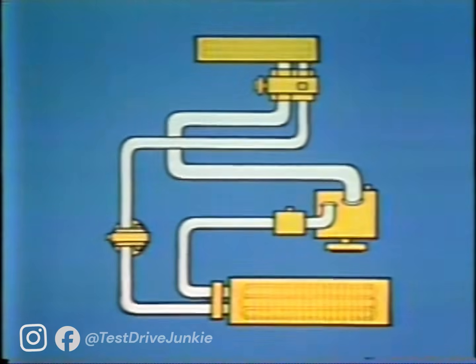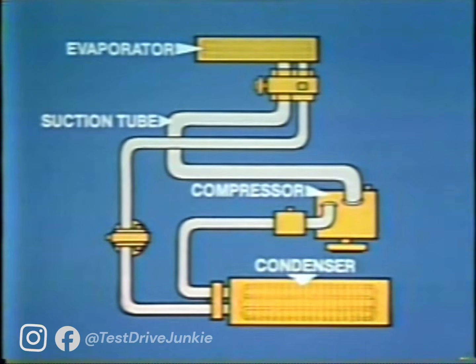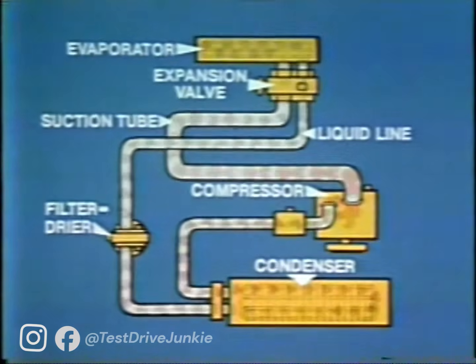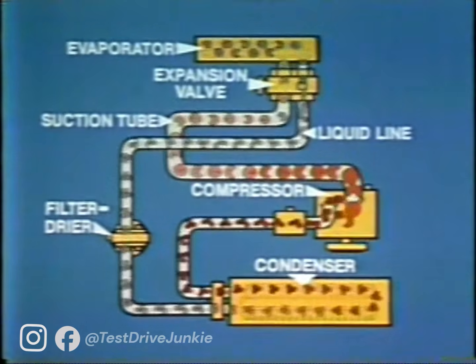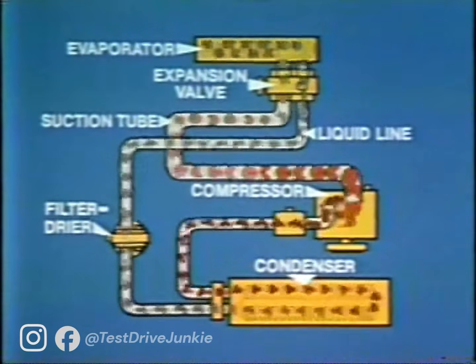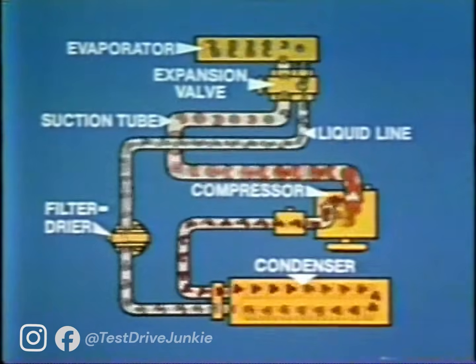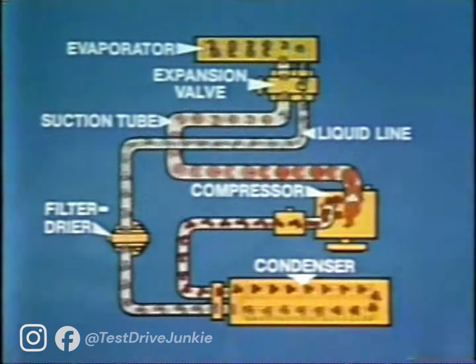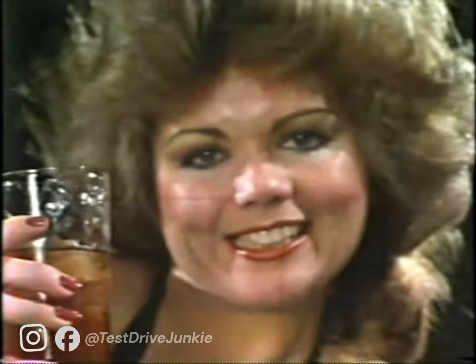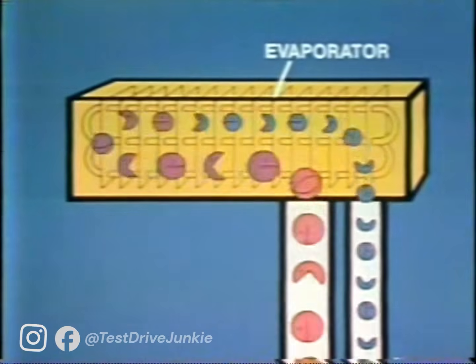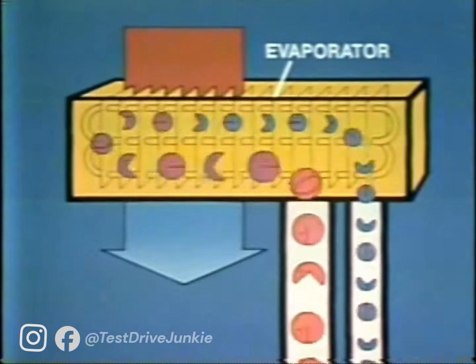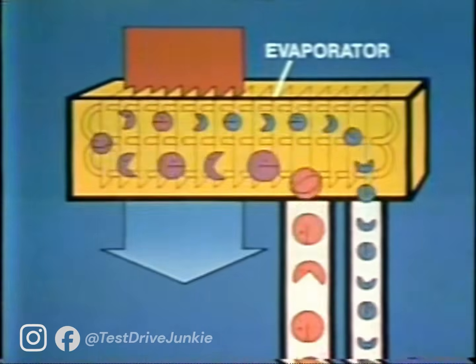All air conditioning systems work on the simple principle that evaporation cools. This is because a large amount of heat energy is needed to change a liquid into a vapor. It takes almost 1,000 times as much heat energy to vaporize a quantity of water as it does to raise the same quantity of water 1 degree. Just as perspiration helps to keep us cool when it evaporates on our skin, the refrigerant vaporizing in the evaporator absorbs heat from the air flowing past the coil. Refrigerant evaporates very readily, so it absorbs heat much faster than evaporating water.